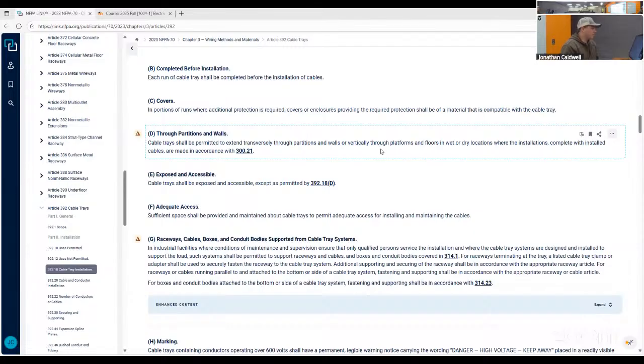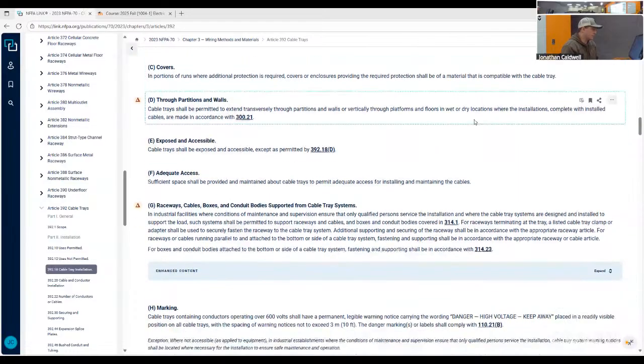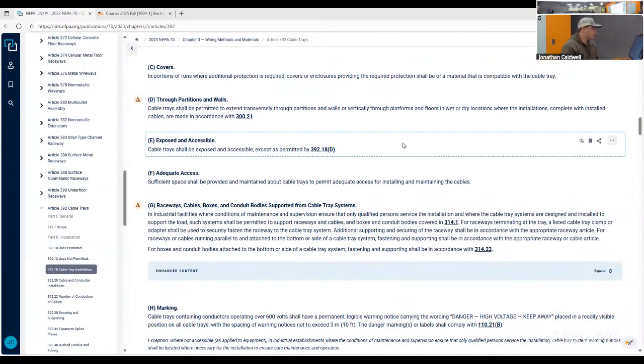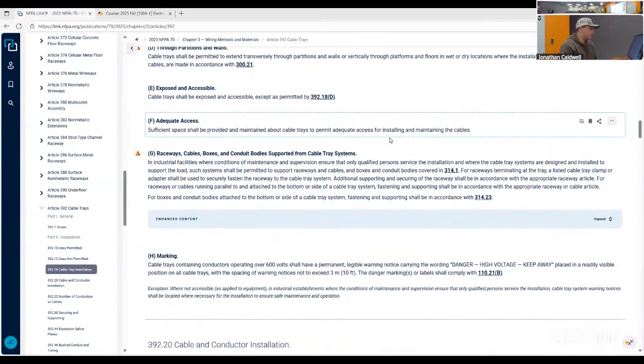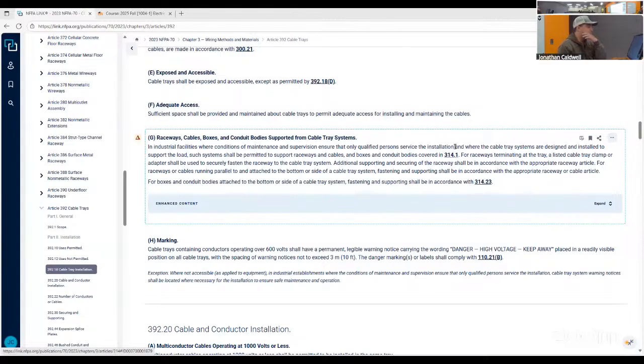Okay, through partitions and walls, cable trays shall be permitted to extend transversely through partitions, just the exact same way as the wireway. Exposed and accessible: cable trays shall be exposed and accessible except as permitted by 392.18, and shall have adequate access. Raceways, cables, boxes, and conduit bodies supported from cable tray systems. This just goes on saying that it's common in industrial facilities, and just leave it at that.